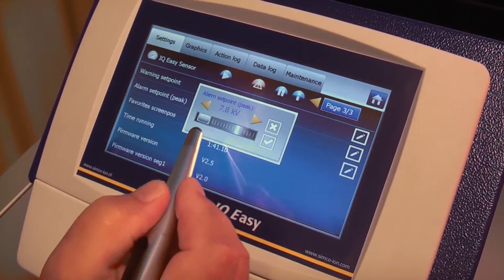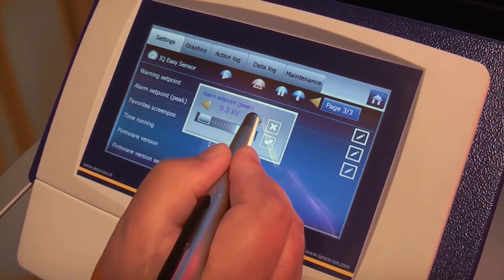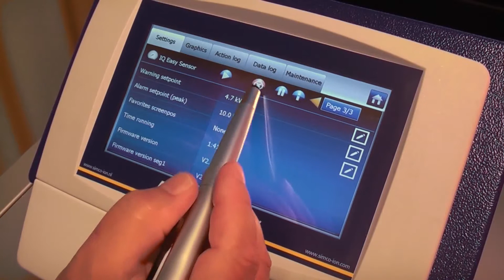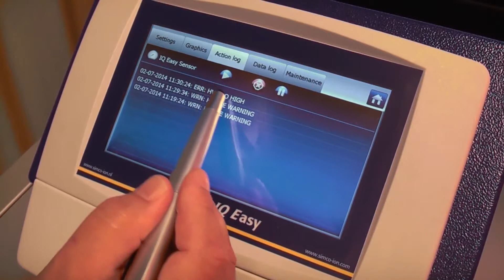When I set that below the measured value, for instance, maybe 10 kilovolts, now the little icon changes from a warning to an alarm. And when I go into the action log, okay, it also will tell me there was a warning, but now it has been overruled by a higher level, which means a warning, an error, the high voltage is too high.